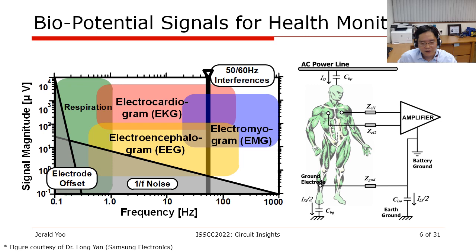Now that you have seen the system-level challenges, let's look at the biopotential signal in more detail. I have shown three exemplary biopotentials: electrocardiogram (EKG) from your heart, electroencephalogram (EEG) from your brain, and electromyogram (EMG) from your muscle. The first thing you'll notice is that the amplitude of these signals is very weak. EEG, for example, is in the orders of microvolt; EKG goes to around millivolt.